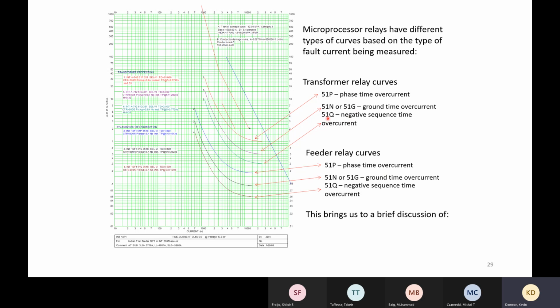And then I get negative sequence. You didn't see negative sequence in electromechanical relays a whole lot just because it was hard to wire up, so people didn't use it that much. But with microprocessor relays, it became pretty easy to do because it's built into the same box. So I can do all these different functions. Remember back in the electromechanical where I showed you I had three 51Ps and one ground? Well, now I've got a single 51P that operates off any one phase. I've got grounds and I get negative sequence, and most manufacturers actually give you multiple levels of these. I may have up to 4 or 5 51Ps, so I can use them for different things. So there are a lot of advantages of microprocessor relays, on top of, as I mentioned, being able to change setting groups, which is another big benefit.